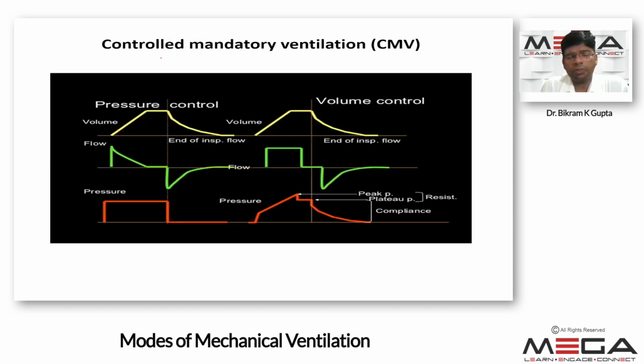Now the first thing is controlled mandatory ventilation. It includes both volume control as well as pressure control. Both of these control modes of ventilation are time triggered and time cycled. In volume control, we have to set the volume, and that volume will be achieved by variable pressure, and the flow will be a constant flow. In pressure control, we have to set the pressure to achieve the target volume.